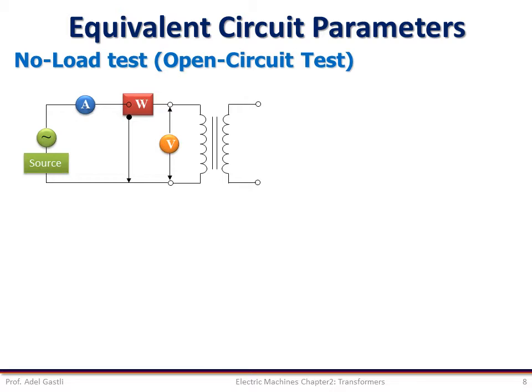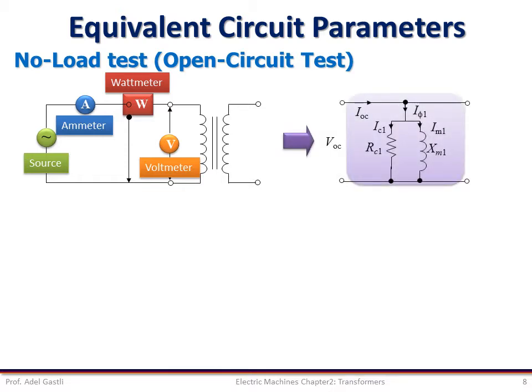During this test, the transformer primary is connected to an AC voltage source at the rated voltage of the transformer, while the secondary winding is left open. We connect one ammeter, one voltmeter, and one wattmeter as shown in the circuit. Under this operating condition, there is no current in the secondary circuit, so we can approximate the equivalent circuit as the shunt branch only.